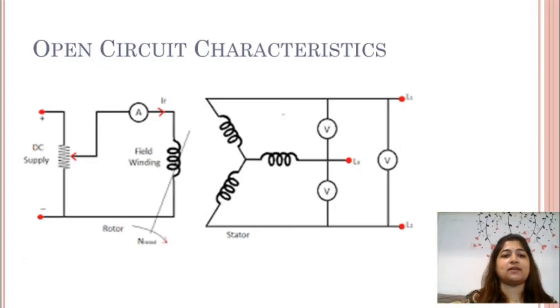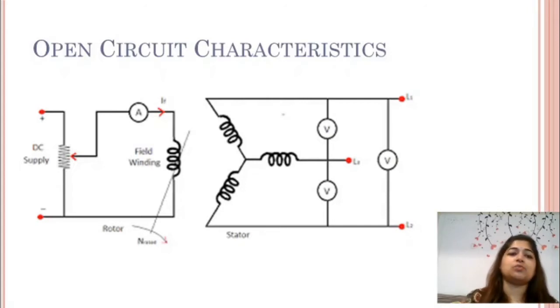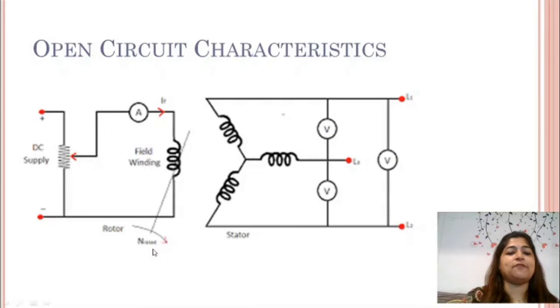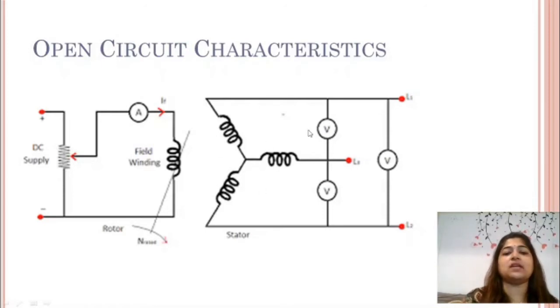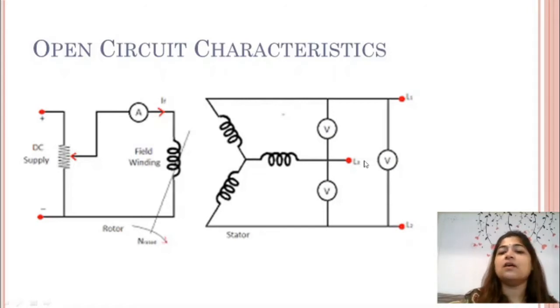Next is to find out the open circuit characteristics. To get the open circuit characteristics you must perform the open circuit test on the alternator. The field winding is given DC excitation separately and rotated by a prime mover at rated speed. The three-phase star-connected armature windings are open circuited — open circuited means there are just voltmeters connected across them, and connecting a voltmeter is as good as an open circuit.